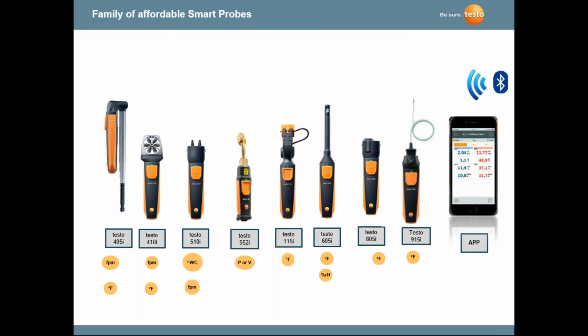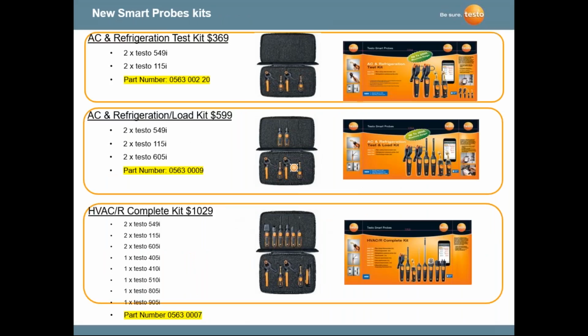In addition to that, you guys may be familiar with some of the individual smart probes that we have. These are used in a variety of applications for HVAC and refrigeration. You've got airflow probes, differential pressure, and pressure probes. You saw the pipe clamp probe. There's a humidity probe which does the wet bulb reading, temperature reading, and the relative humidity reading. Infrared thermometer, and a new one that we just introduced, which has a Type K thermocouple connection. So a lot of new things happening in the digital world, especially with smart probes. You can buy these in kit form, or you can buy these individually.